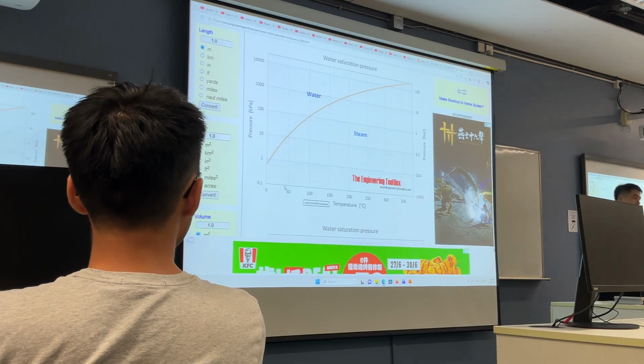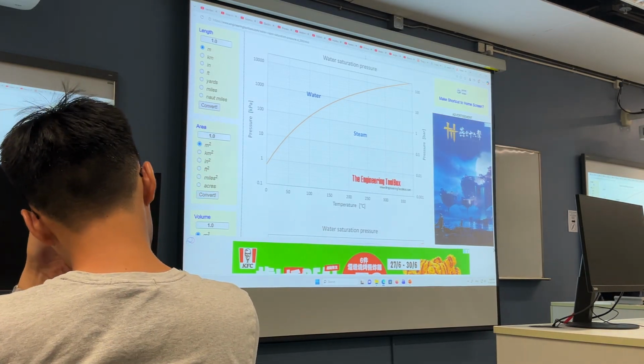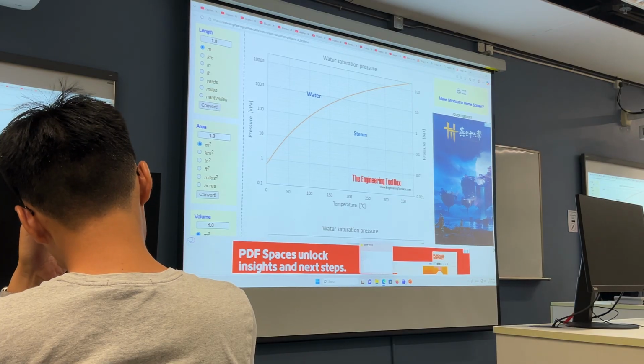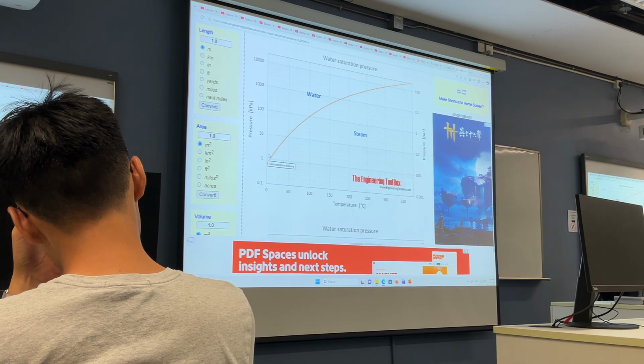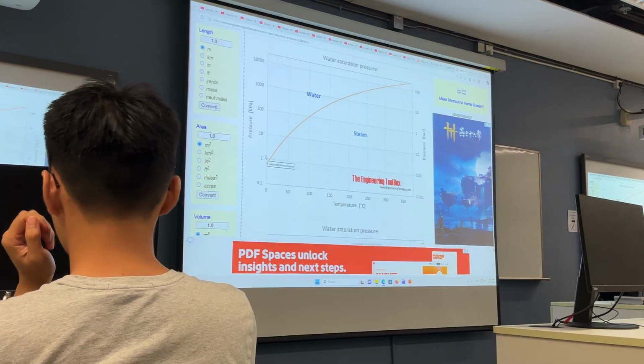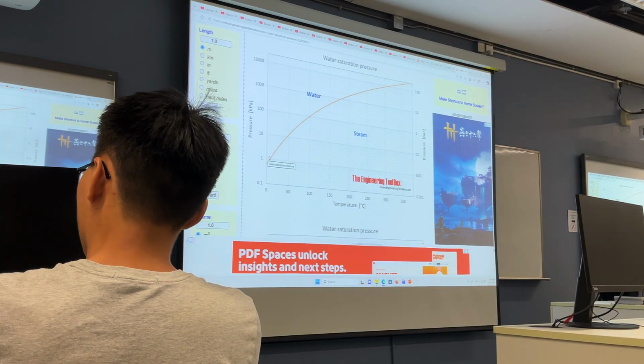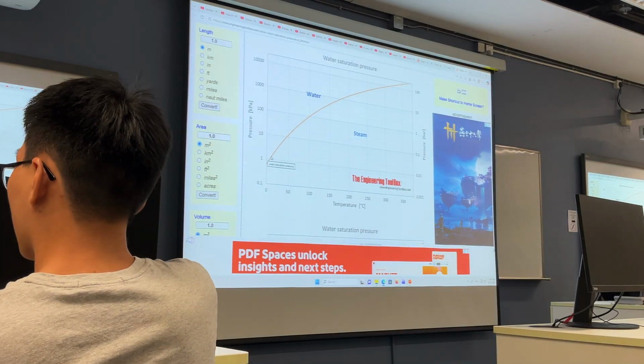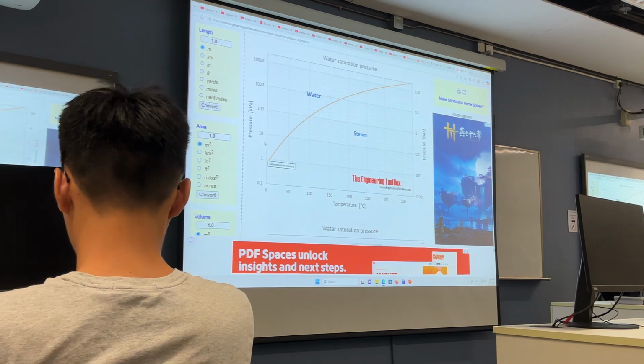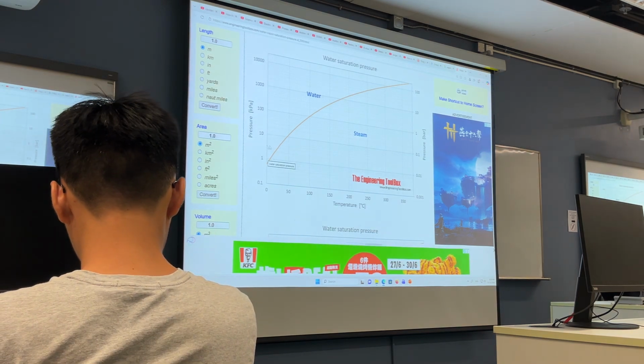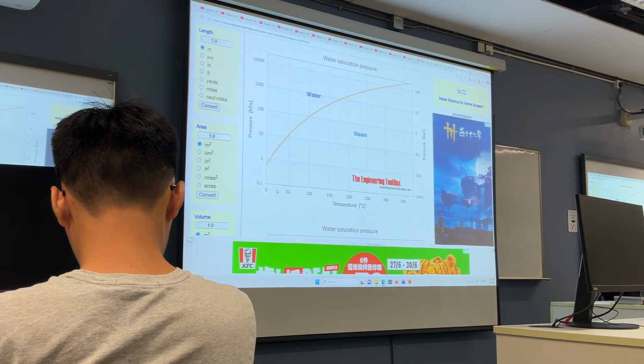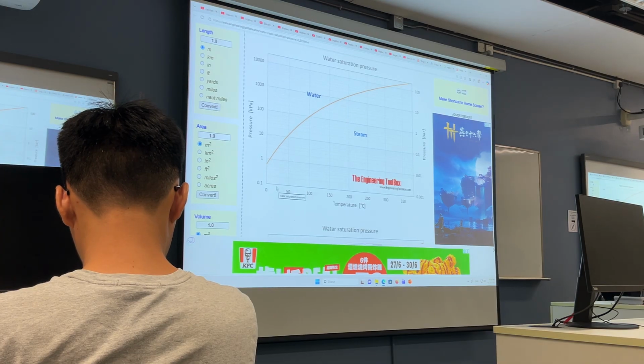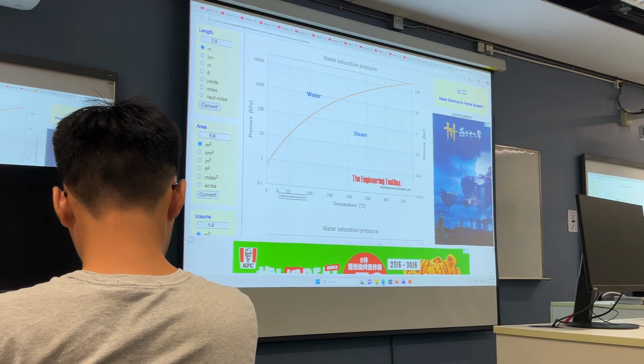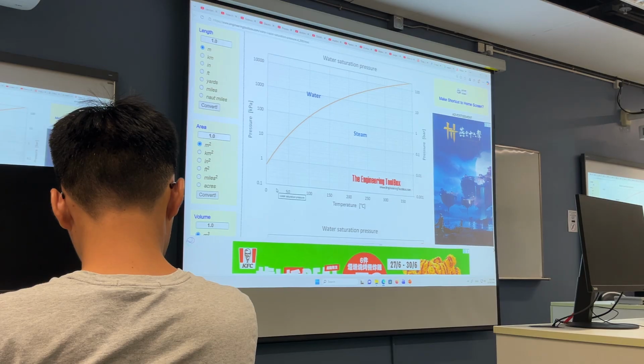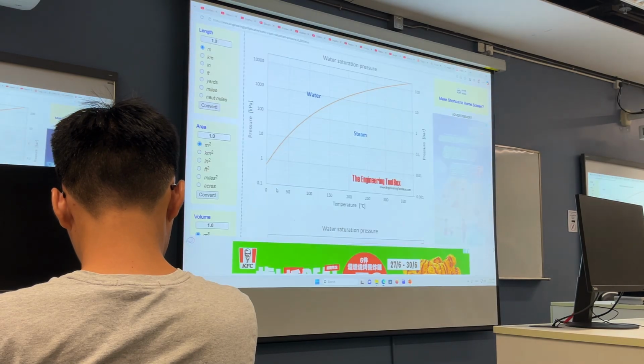So that means if the velocity is fast enough, making the pressure drop to a very low level, for example 2 kPa, or maybe less than 10, say 5 kPa, the water may boil from about 20 degrees Celsius.